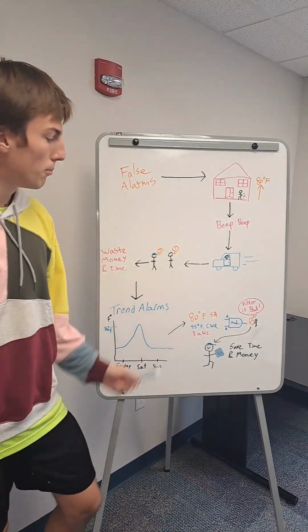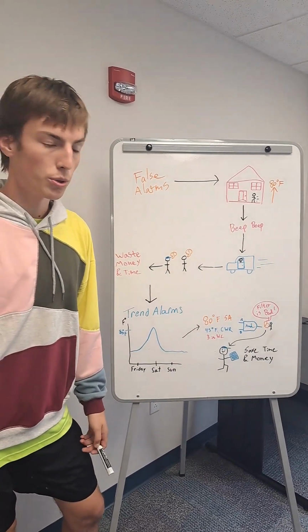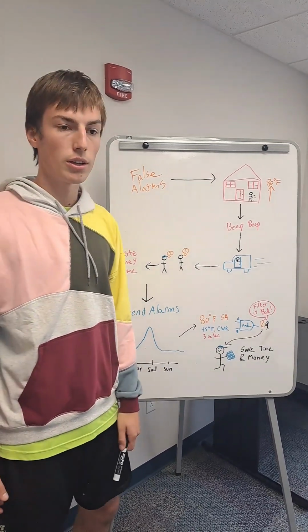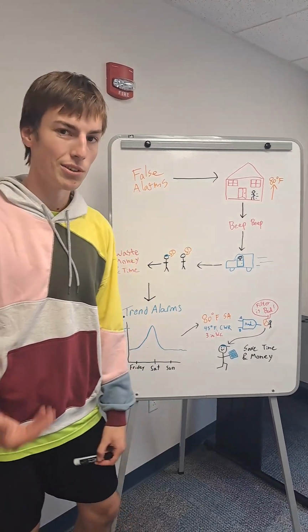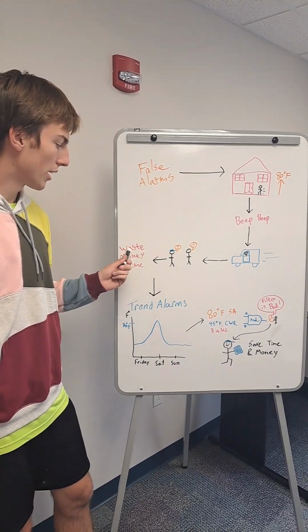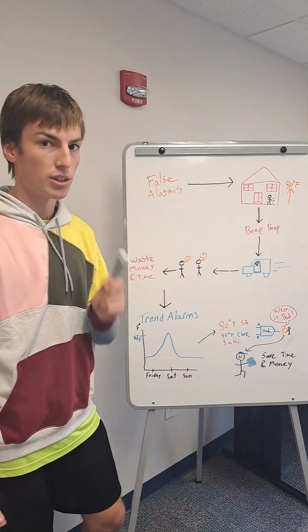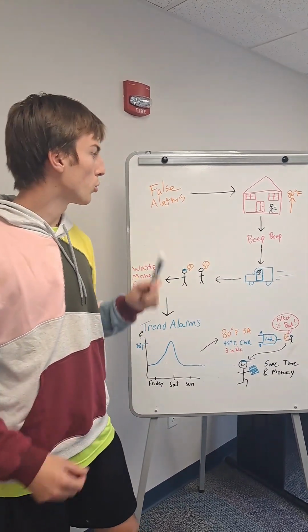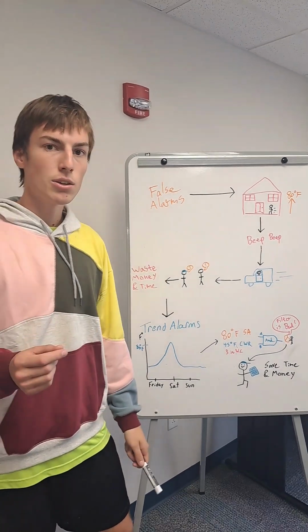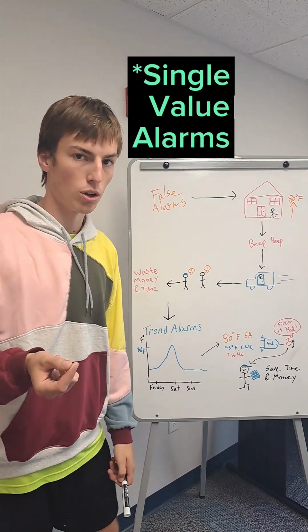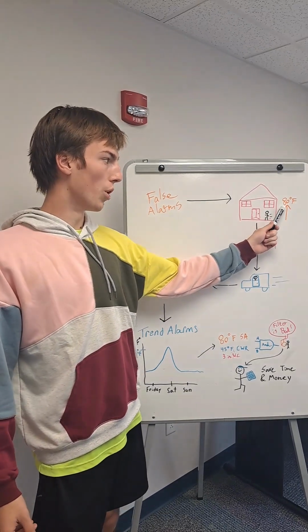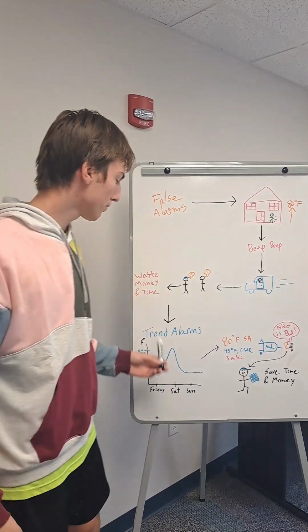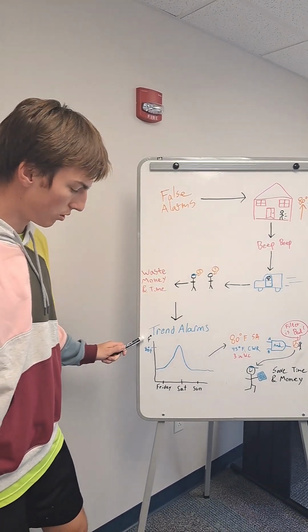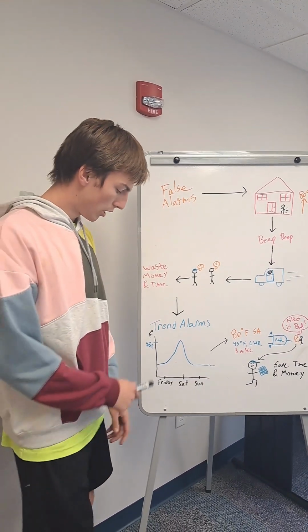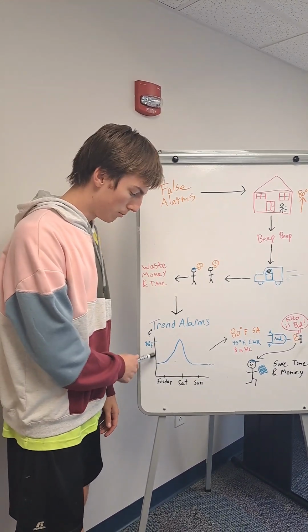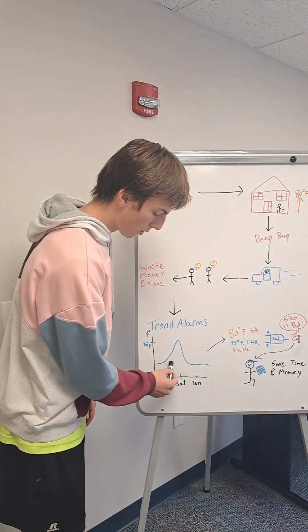When he gets there, the movers are like, "What are you doing here?" And he's like, "Well, isn't the building hot?" They're like, "Isn't the building always this warm?" Because they're not used to it. This wastes the technician's time, it wastes the company's money. So you don't want to use single value alarms that only rely on one thing, temperature. We want to use trend alarms. Trend alarms can either rely on one thing, like temperature, and monitor it over a long amount of time.